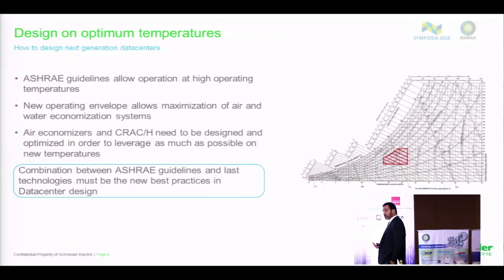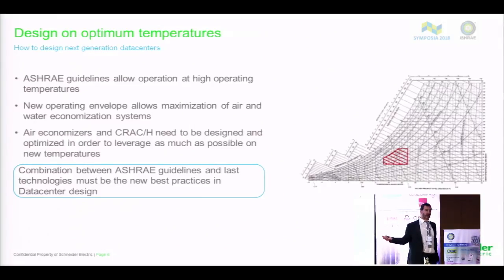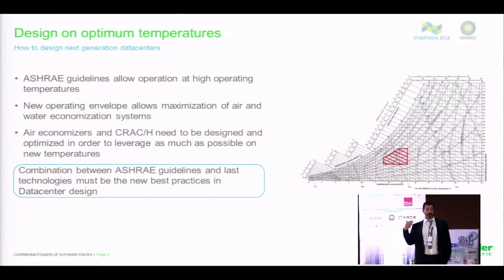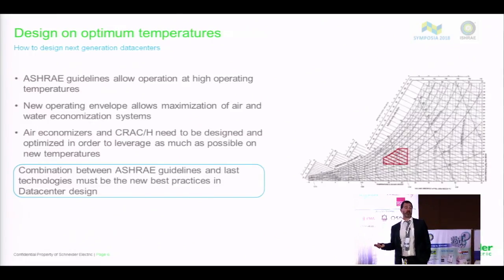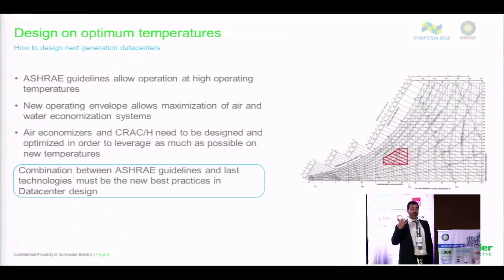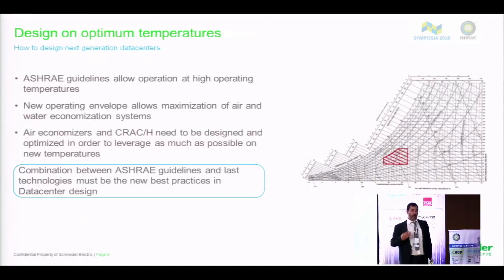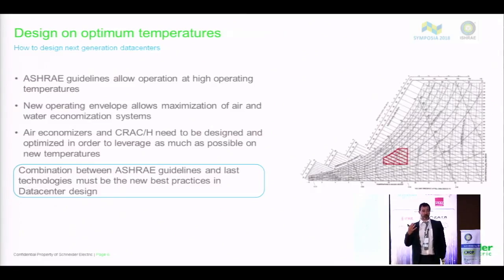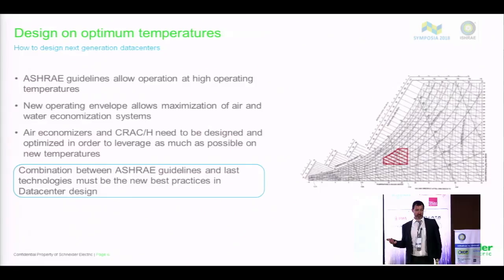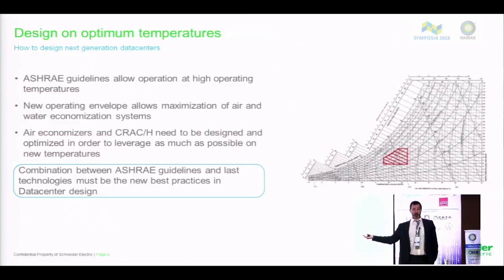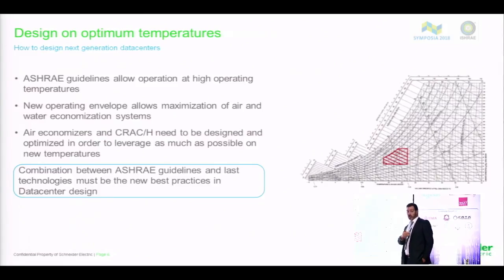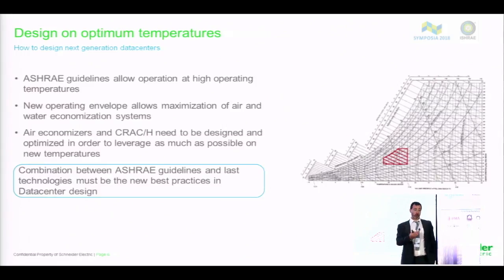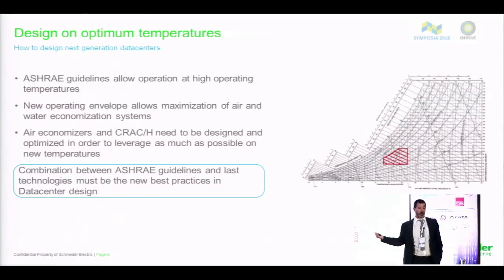Pay attention that when we design at such a high temperature, of course, the thermal inertia in the data center is much lower than in the past. So if we design at 26 and there is any power failure, we need to be aware that all the systems should be restored in less than a couple of minutes, 3 minutes maximum, because otherwise the temperature overcomes the 27, overcomes the edge. So this also reflects the technology that should be used on the chiller and on the air economizer.